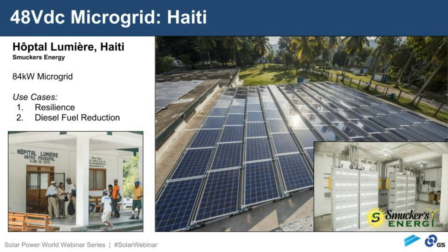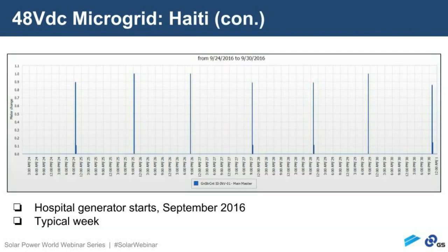So in the next slide, we will look at a graph I like a lot because it shows how that hospital had transitioned from mechanical generation to solar with only, I think, one interesting data point. This was September 2016, just after the construction had ended. It had been running for, I think, a month and a half or so. And sure enough, here's the generator. They used to run on a couple of generators and hydropower pretty much constantly, refueling as they needed. But now we can see the generator just coming online once a day, basically for exercising. And that's great. That's exactly what you would expect if everything was done correctly from the solar and battery design. But what happens next really illustrates, I think, a good design.